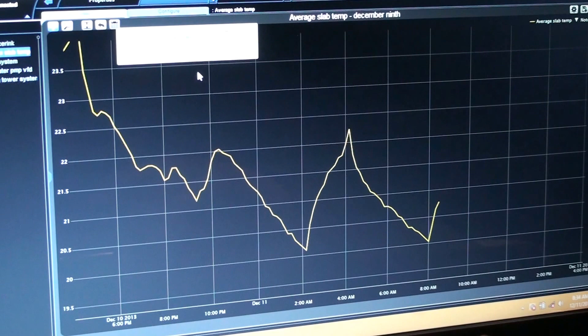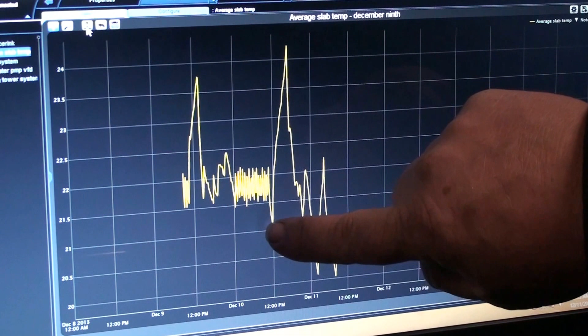This point right here, we ran the chiller down a little bit in temperature because we knew we were going to have it off because we had to make some adjustments in piping. And that shows from the time it went off to the time that we restarted the chiller, which the temperature, it looks like a lot, but it's not. It got up to 24.25 degrees.